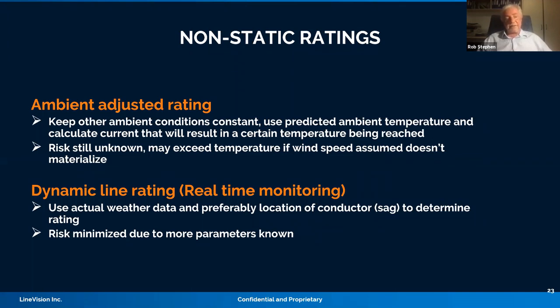The other one is the dynamic line ratings. Now you can actually use actual weather data, or preferably the location of the conductor. This is done in many ways, and there's a brochure out on what we call real-time monitoring within CIGRE, which defines a number of methods which you could use, and LineVision has one of those methods. There are a number of these methods which actually measure the conductor position in space. Then you use weather data to determine the current that will result in a particular conductor reaching the design temperature over the next hour, and you can actually go down to the next half hour.